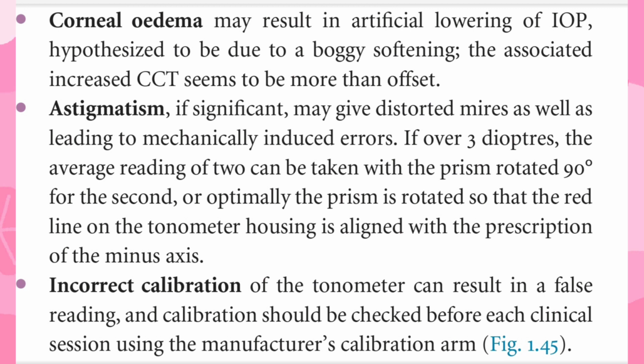Astigmatism, if significant, may give distorted mires as well as leading to mechanically induced errors. If over 3 diopters, the average reading of 2 can be taken with the prism rotated 90 degrees for the second, or optimally the prism is rotated so that the red line on the tonometer housing is aligned with the prescription of the minus axis.